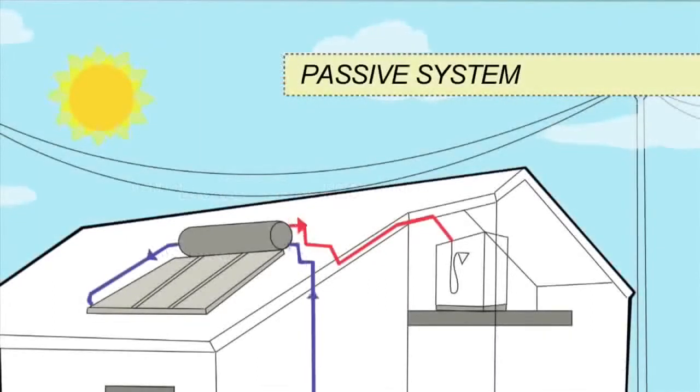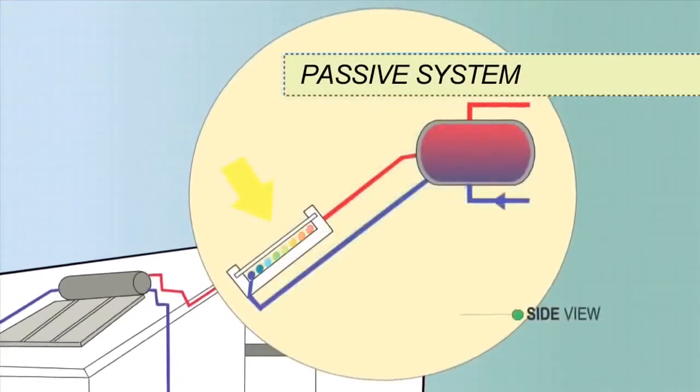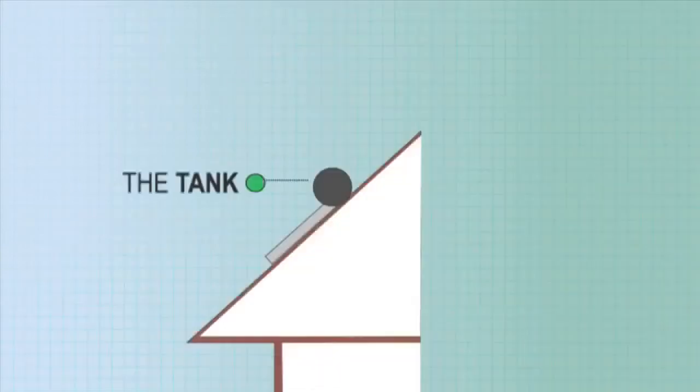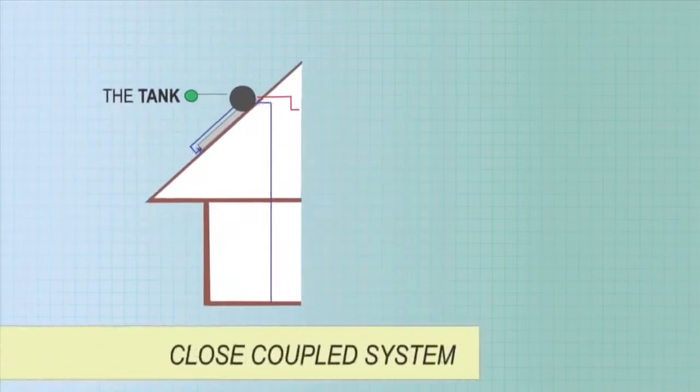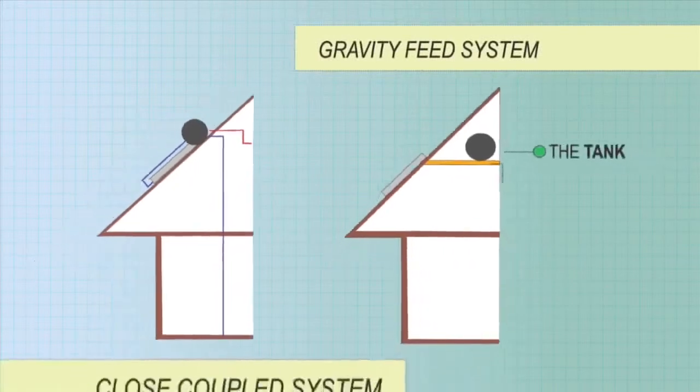In passive systems, also known as thermosiphon systems, the tank sits above the collectors. Cold water sinks into the collectors whilst warmer water rises unassisted from the collectors into the tank. The tank may sit on the roof with the collector, a close coupled system, or within the roof cavity above the collector, a gravity feed system.